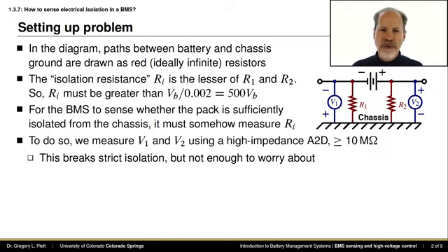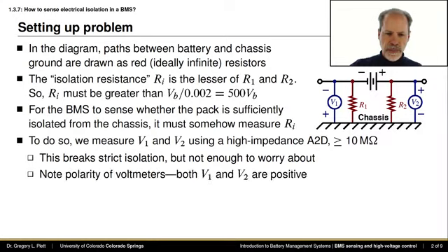We're making a pathway between one terminal of the battery pack and the chassis of the vehicle. But because we specify that the resistance of the voltmeter must be greater than 10 mega ohms, we ensure that less than 2 milliamps of current will flow for most batteries unless the battery voltage is extremely high. So this is not breaking isolation according to our specification by placing this voltmeter in the circuit.